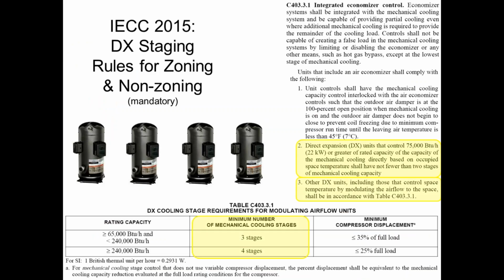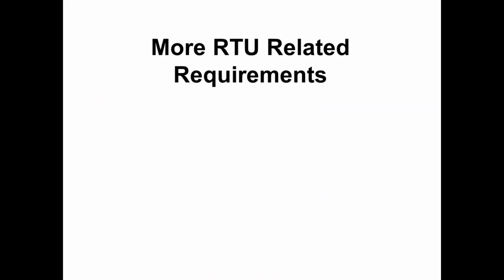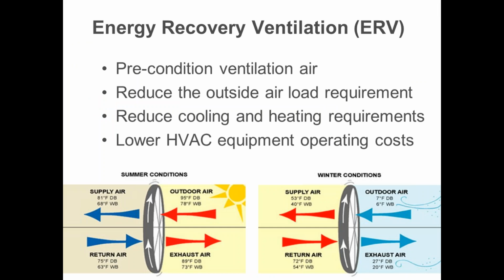All right, last few concepts here. ERVs: we don't have time to talk about that either, because ERVs are a whole other hour in and of themselves. But ERVs save energy by taking energy from my exhaust air stream and transferring it to my ventilation air stream. So obviously the more ventilation air or exhaust air that I have, the more energy savings potential there will be. If you don't have any ventilation air or exhaust air, this doesn't do anything.